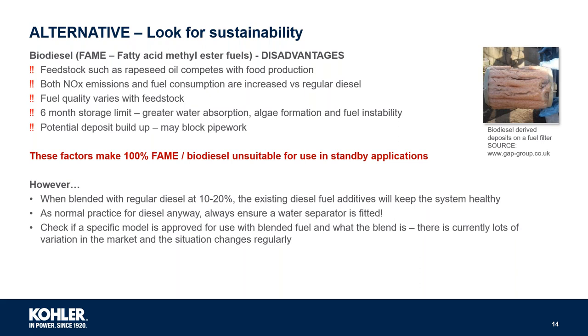Whilst it absorbs more water than regular diesel, the biggest problem is that algae can form in the fuel and it suffers from fuel instability. The deposits within the fuel have potential to block pipework. In fact, the picture on the right-hand side of your screen shows a filter removed from a diesel genset engine running on FAME biodiesel, and the filter is completely blocked.